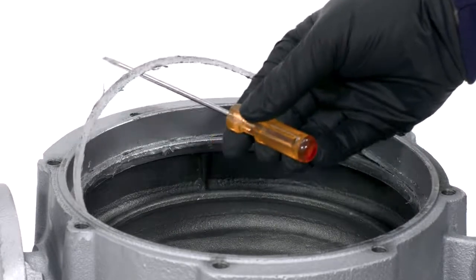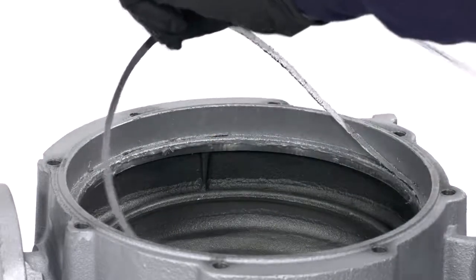With the pump casing removed, you can inspect the graphite laminated gasket for wear and replace if necessary.